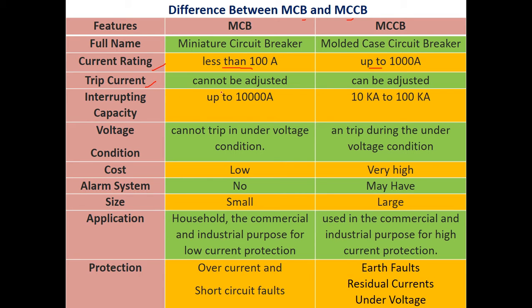Regarding trip current adjustment, the trip current cannot be adjusted with MCB, whereas the trip current can be adjusted with MCCB. For interrupting capacity, the interrupting capacity of MCB is up to 10,000 amperes, whereas for MCCB it is in the order of 10 kilo-amperes to 100 kilo-amperes.